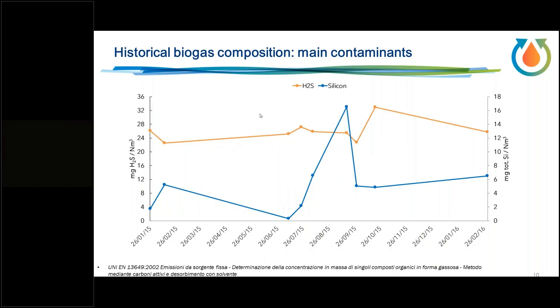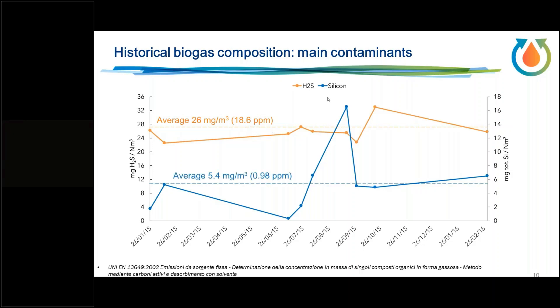Over one year of measurement, the sulfur in this biogas is almost entirely H2S, with an average of approximately 26 mg/m³, equivalent to around 19 ppm. For silicon, the most abundant siloxane is D5 — a cyclic compound — at an average of 5.4 mg/m³, equivalent to around 1 ppm. These are the starting values that must be cleaned to reach the solid oxide fuel cell producer's target specifications.